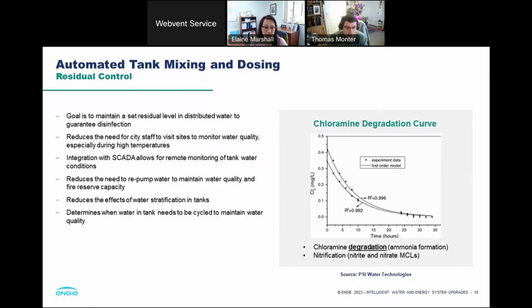These new tank mixing systems add just enough chlorine, or a little ammonia to take up free chlorine, to make sure monochloramine levels remain at their set points even during high temperatures. Under normal conditions without the boosting systems, you'd see quality degradation and the formation of nitrifying bacteria. This has really allowed the city to maintain water quality in their tanks, particularly their larger tanks at the sites. They can now leave water in those tanks for 2 to 3 weeks rather than the 3 to 4 days they were having to previously.